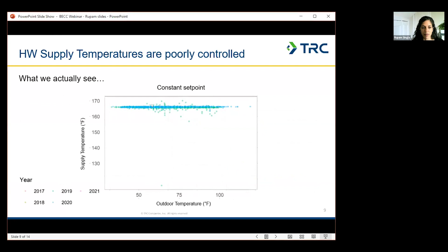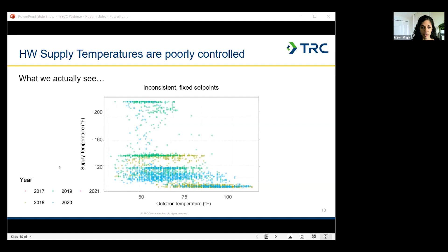This is another example. This is an example of an inconsistent fixed temperature set point. So in this case, it looks like the set point is actually manually controlled. So it's clear that there were actually several different set points throughout this 5-year period. So it's likely that the set point was manually changed several times. Like maybe the set point was manually increased upon a perceived need for heating, and then maybe some warmer weather came, and then it was manually decreased for the warm weather. But then each time the change was made, that change stuck around for quite a while before it was manually changed again.